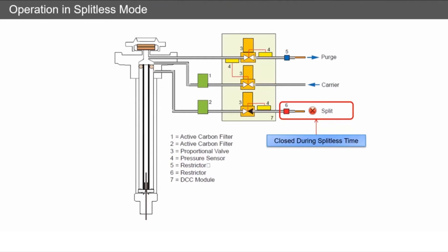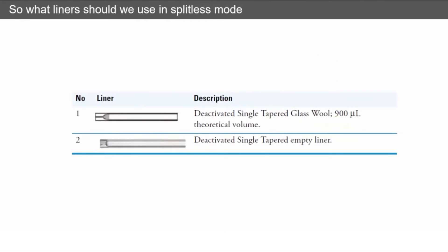Typical liners we're going to use: a single tapered liner to focus everything onto the column. Depending on whether we're doing hot needle injection or cold needle injection, we'll have glass wool or not. Typically these liners have a volume of about 1 mL, so we've got good volume.